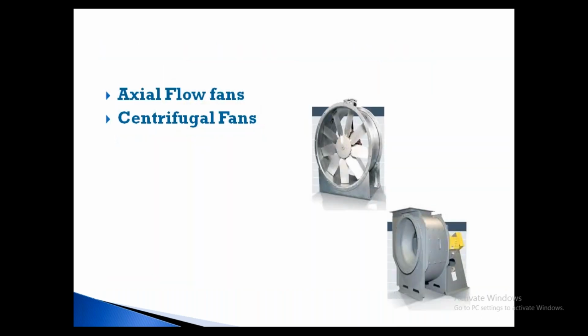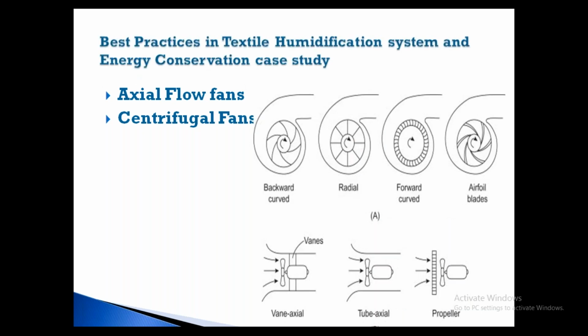What is the difference between an axial flow fan and a centrifugal fan? He brushed over the fan aspects, expecting Ashok sir to dwell a little bit on the fans. I think he mostly covered the centrifugal fans, explaining aerofoil blades, mostly backward, forward, radial. The four types of impellers are backward curved fans, radial fans, forward curved fans, and aerofoil blades. Aerofoil is the most efficient one. Backward and radial, that efficiency chart I'll explain in the next slides.